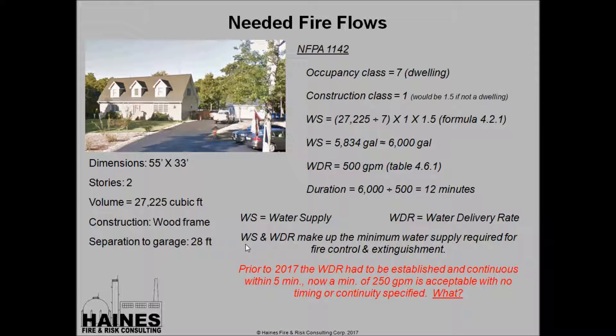The WS and WDR of the NFPA 1142 method are defined as the minimum water supply required for fire control and extinguishment. Prior to 2017, the water delivery rate had to be established and continuous within five minutes of the first apparatus arriving on scene. In 2017, the committee changed this to just a minimum of 250 GPM with no timing or continuity specified. I think they've essentially said that it's okay to be at ISO 9 and be happy with it.